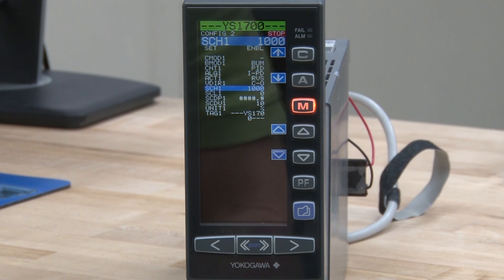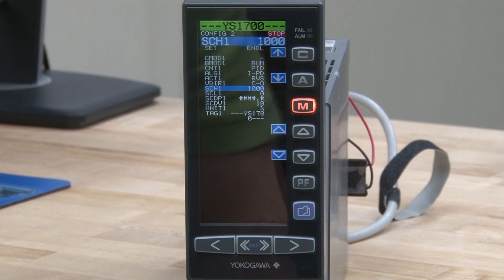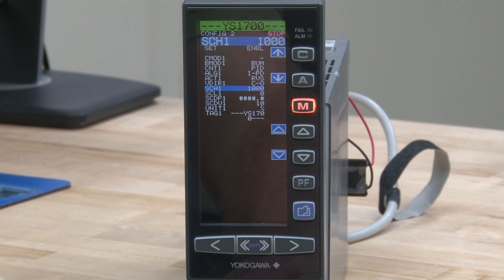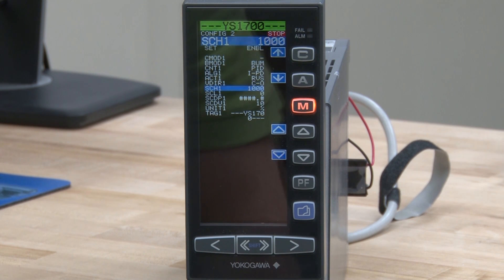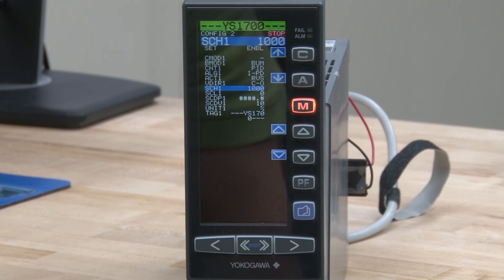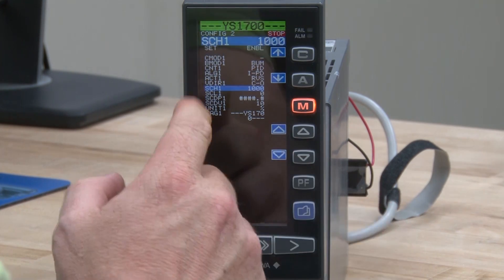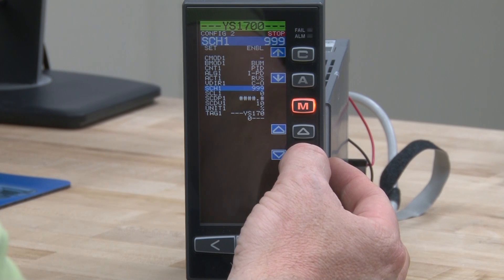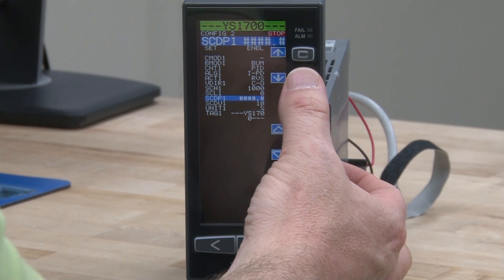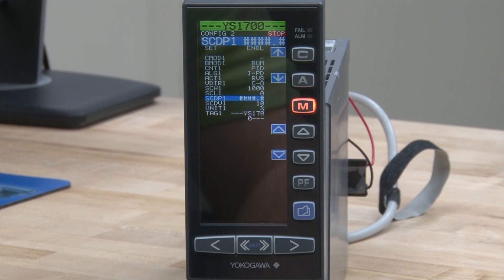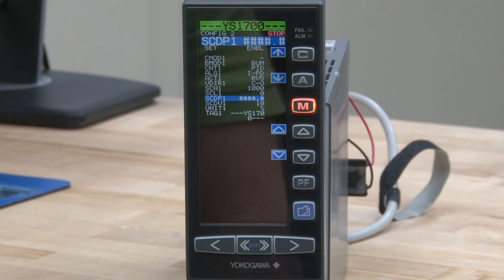For this example, let's say our 20 milliamp or 5 volt signal represents 500, and our scale low is going to be 0 — so our 4 milliamp or 1 volt is going to be equivalent to 0 GPM in this case. First, let's go down to SCDP and take a look at the decimal point position. The way it is now, we have one number to the right of the decimal, and that's fine.